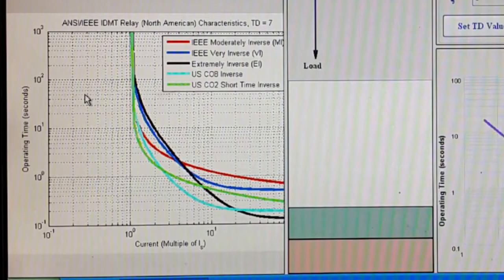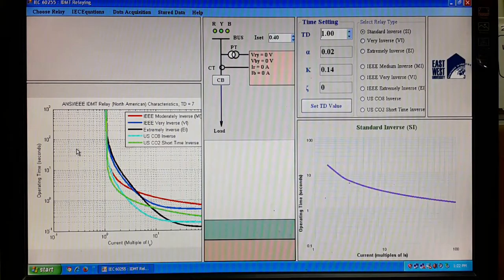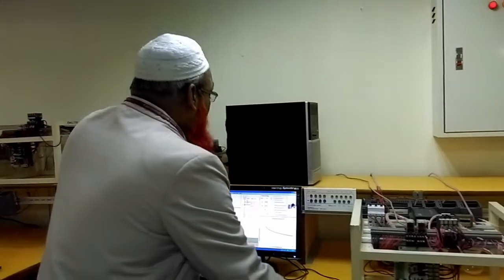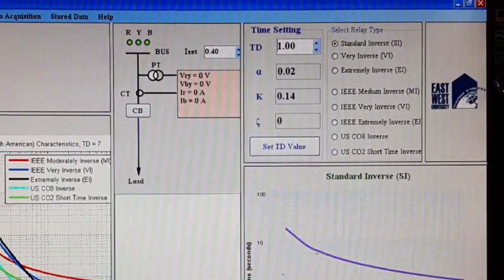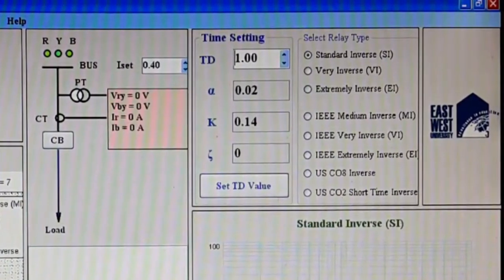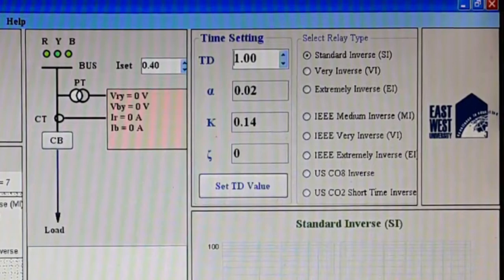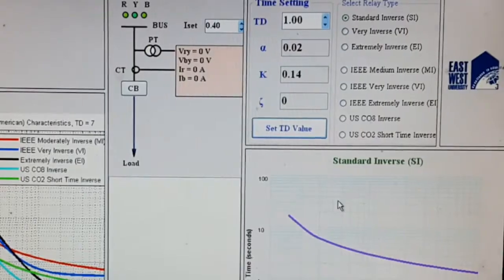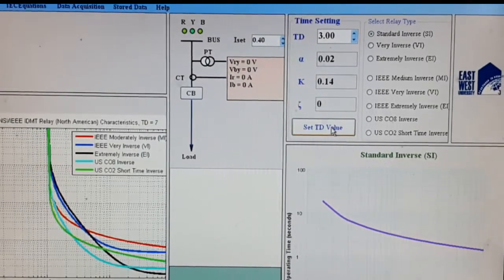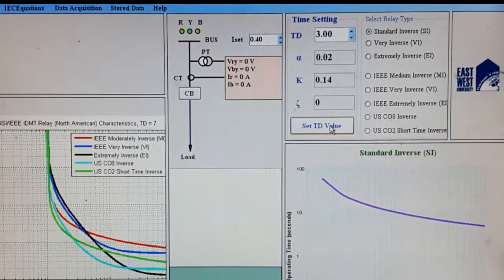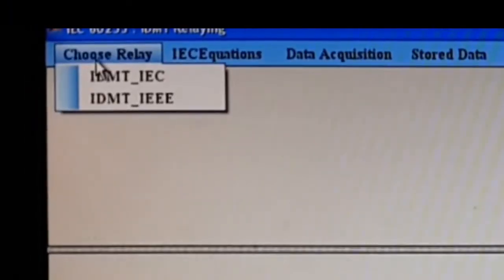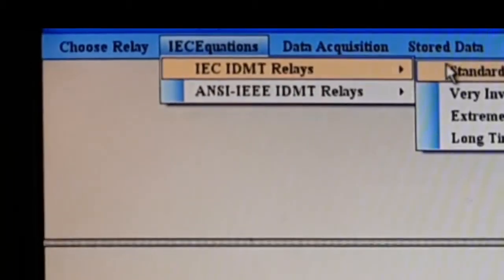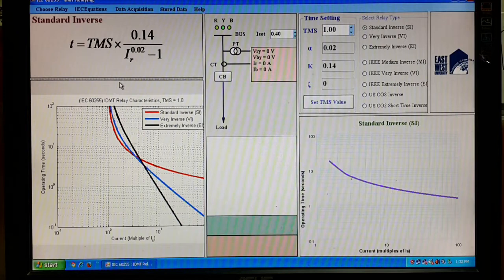The x-axis is current and the y-axis is operating time. All these curves can be simulated here using online data. On the right side, you can choose the relays — three IEC relays and five IEEE relays. If you choose a particular relay, for example standard inverse, this is the curve. If you change the TD value, the curve moves upwards. The equation for the selected relay is shown on the left side.